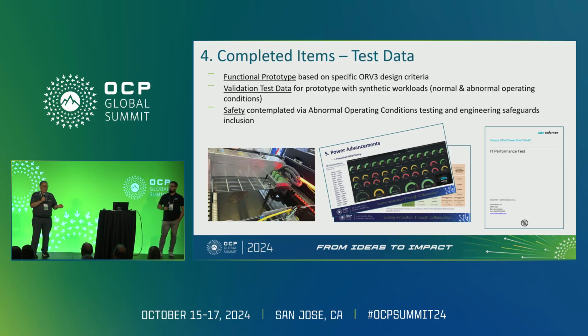That's what we can do. We're actually going to end up pushing this power supply that's a 3.6 kilowatt power supply to somewhere close to 6, 7 kilowatts. The only thing I have to be careful of is the component ratings for the currents, okay? I have to take that into account. We've still got more testing to do, but we've shown that it can be done. As with the bus bars that can handle almost 2 times, the power supplies can do the same thing, because the fluid is so efficient at cooling compared to air.